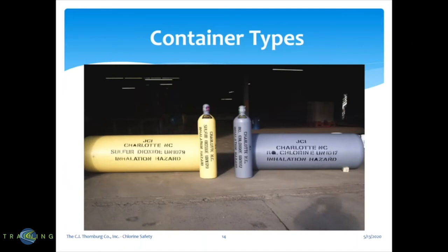Container types. There's chlorine and sulfur dioxide — chlorine cylinders are gray in color. You have a 150-pound cylinder and also a one-ton cylinder. Our supplier is Jones Chemical Incorporated, and we get ours from their Barberton, Ohio location. The ton container DOT spec number is DOT 106A500. It's about 82 inches in length and 30 inches in diameter, weighing between 1,100 and 1,600 pounds empty.